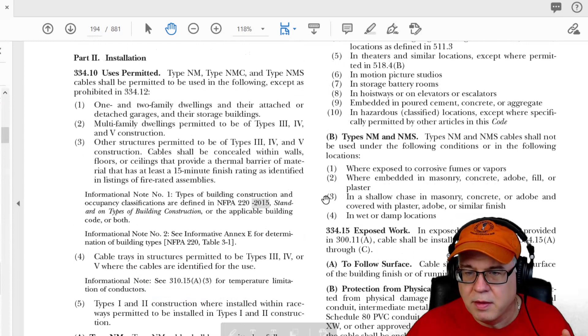Here it says it can be in exposed or concealed work, that's not a problem. But over here where it says type NM, under the not permitted section, 334.12, it says it's not permitted in wet or damp locations, right there.